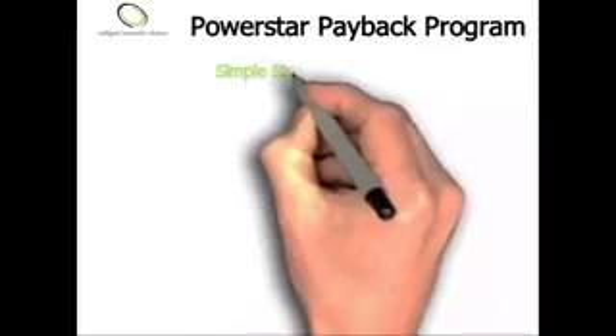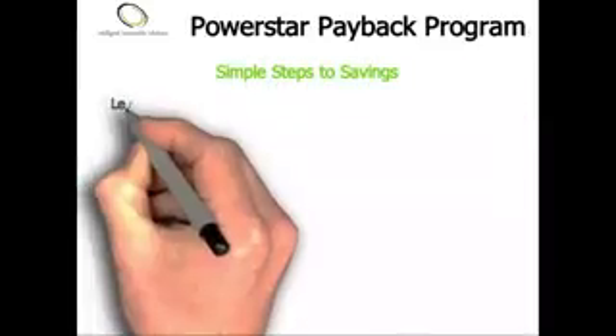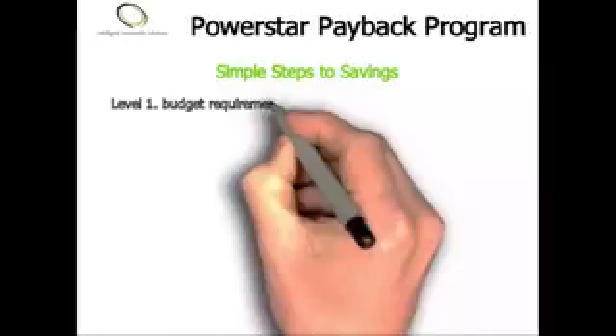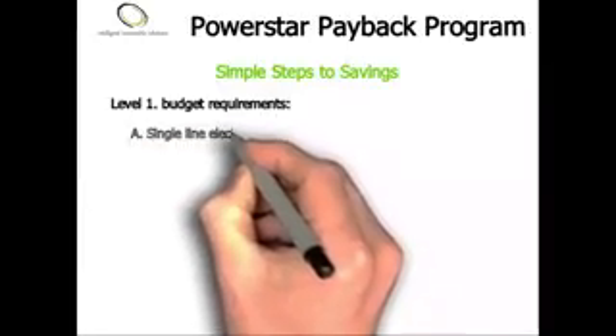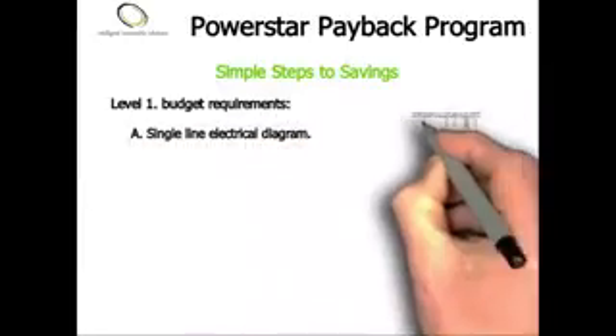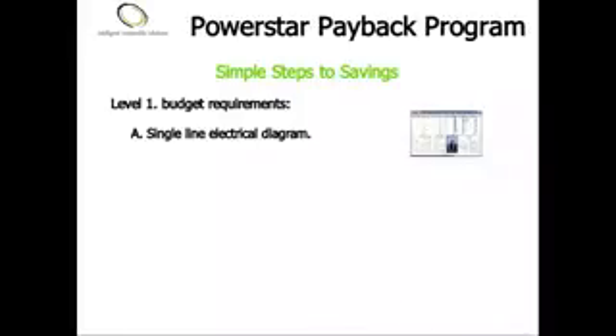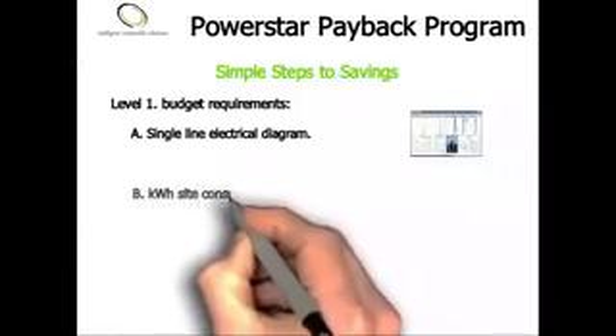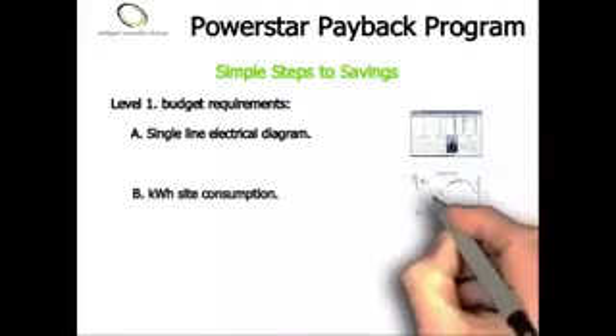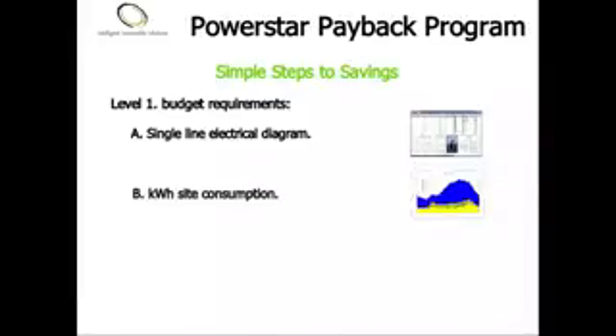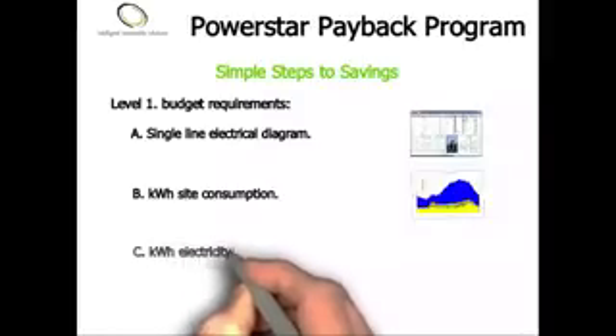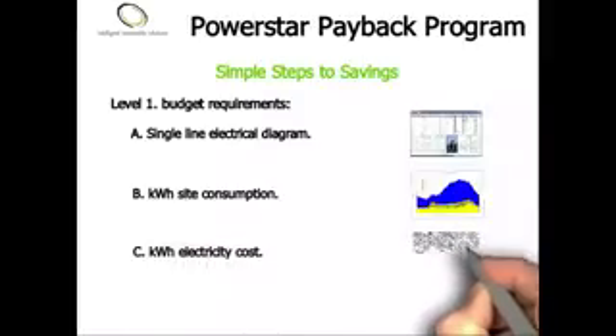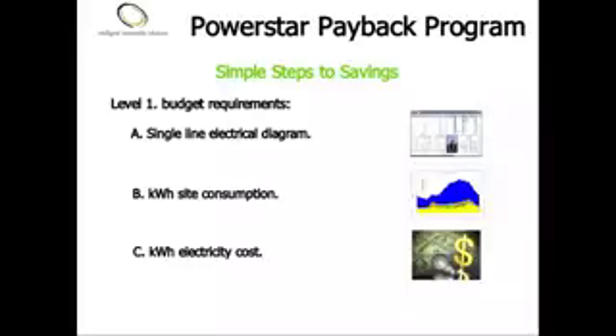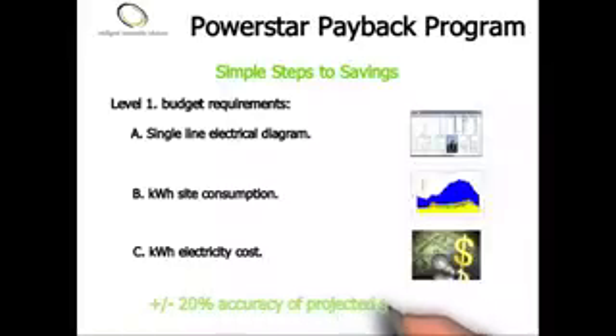Intelligent Sustainable Solutions has introduced a simple three-step program in order to identify and simplify the process of quantifying what the opportunity savings on the target site will be. To meet the information required for us to budget for Level 1, the best start is for us to receive a single-line electrical diagram of the site or specific building. We then would like to see the kilowatt-hour consumption, ideally from the electric bill. And of course, the kilowatt-hour electricity cost. And from this information, we're able to give you plus or minus 20% accuracy of projected savings.